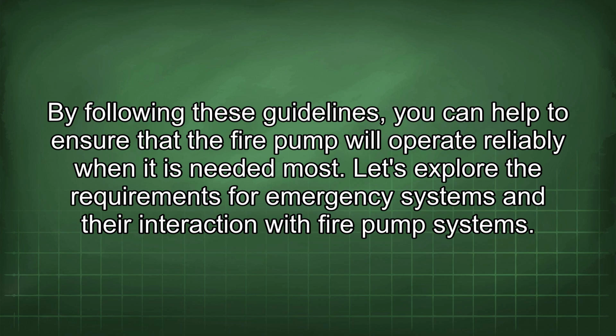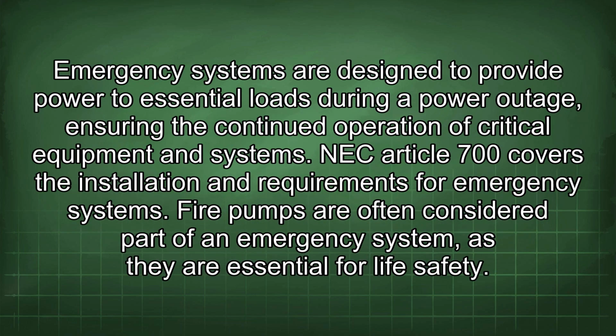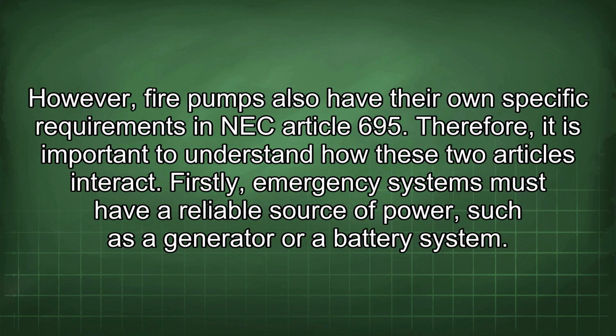Let's explore the requirements for emergency systems and their interaction with fire pump systems. Emergency systems are designed to provide power to essential loads during a power outage, ensuring the continued operation of critical equipment and systems. NEC Article 700 covers the installation and requirements for emergency systems. Fire pumps are often considered part of an emergency system, as they are essential for life safety. However, fire pumps also have their own specific requirements in NEC Article 695. Therefore, it is important to understand how these two articles interact.